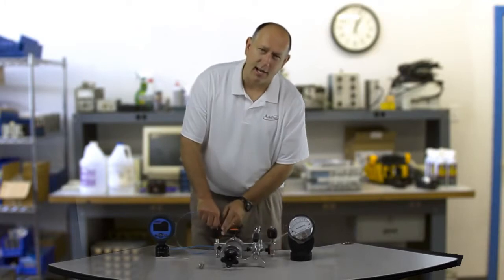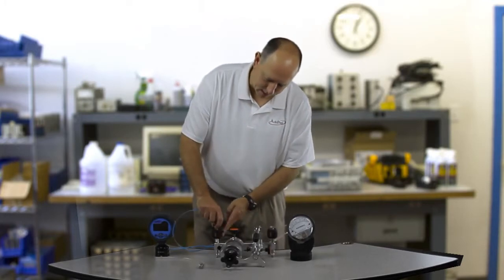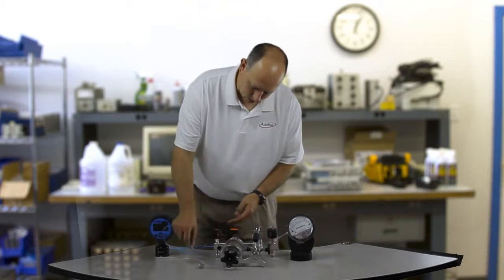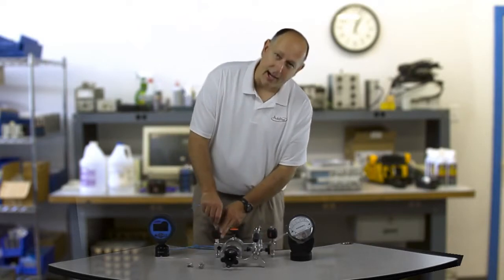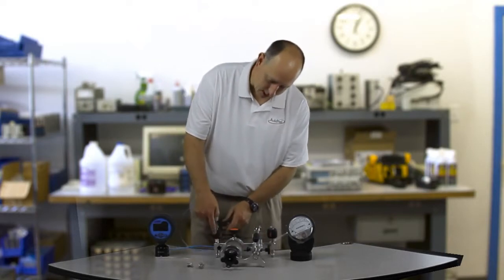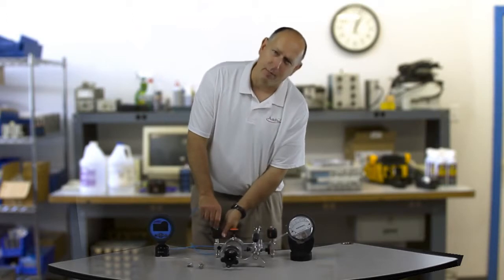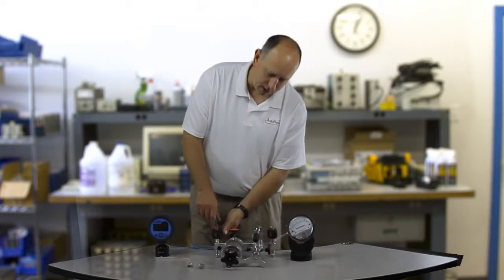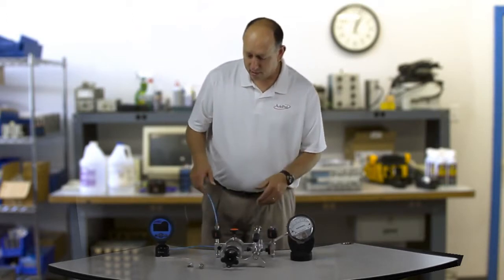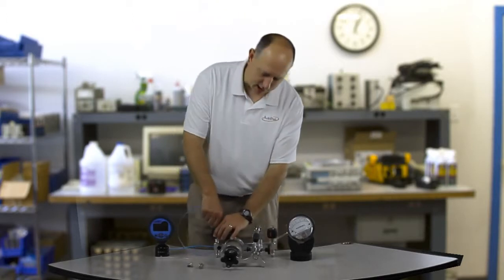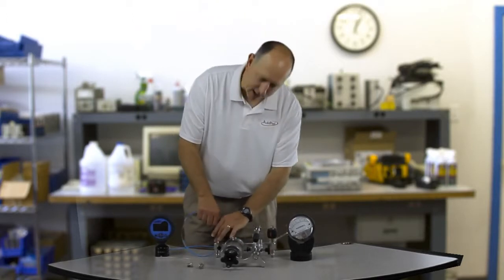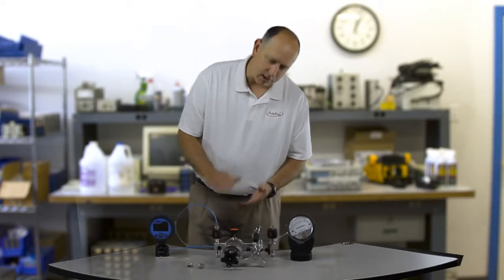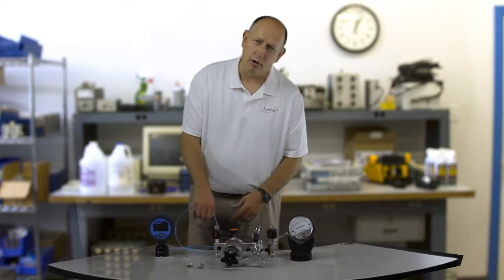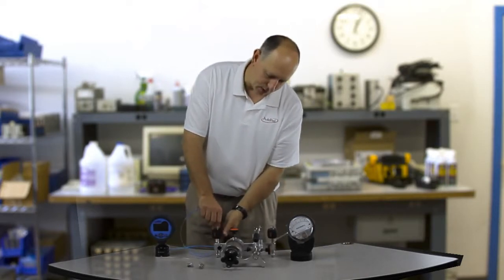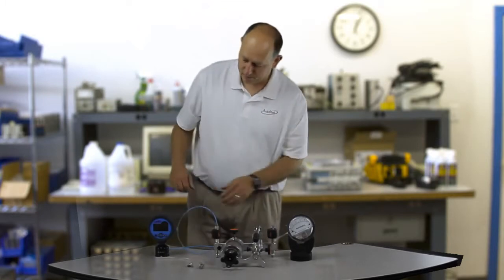Now I'm going to hook the high sides up to the pump, starting with the reference. One of the really nice things about Additel pumps is these quick disconnectors - I don't need tape or wrenches, I just put it in finger tight and screw it down. A lot of customers like to clamp down and screw it in tight, but that smashes the rubber O-ring and shortens its lifespan. If you just put it in finger tight, that's plenty good.